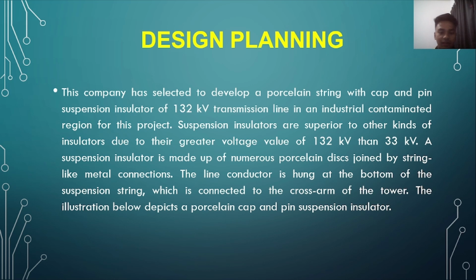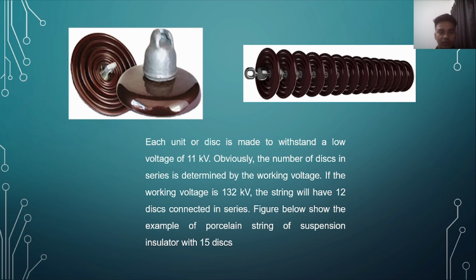A suspension insulator is made out of numerous porcelain discs joined by string-like metal connections. The line conductor is hung at the bottom of the suspension string, which is connected to the cross arm of the tower. So this is our circuit for the cap and pin insulator. Each unit is made to withstand a low voltage of 11 kV. The number of units in series is determined by the working voltage. If the working voltage is 132 kV, the string will have 12 discs connected in series.